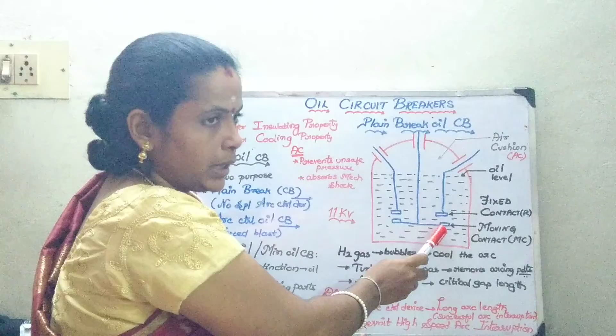The air cushion serves two purposes. Under normal conditions, the fixed and moving contacts stay apart. But whenever a fault occurs, an arc is struck between the fixed and the moving contacts. As a result, because of this arc, the oil vaporizes and forms hydrogen gas bubbles. These hydrogen bubbles, together with the oil, try to quench the arc. The turbulence produced by the gases helps in removing the ionized particles from the arcing path, thereby quenching the arc. So this is the normal procedure followed.